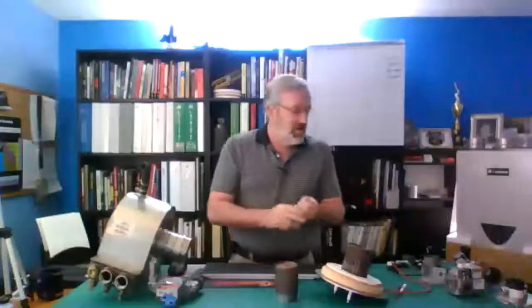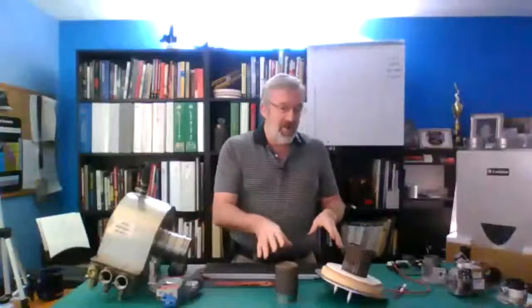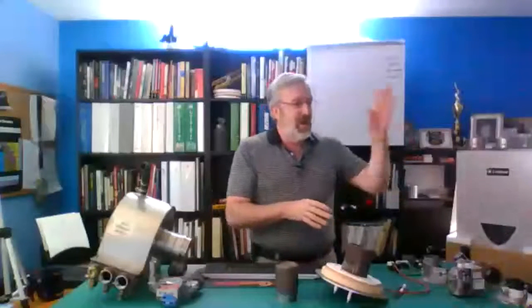We can do a combustion analysis, but we never want to adjust the gas valve if we have not cleaned the burner. So clean your burner if you have to. So if you think I got spark, I've got fuel, where am I going next? If I got a boiler that's 3, 4, 5 years old, and I say to the customer, hey, when did you clean it?